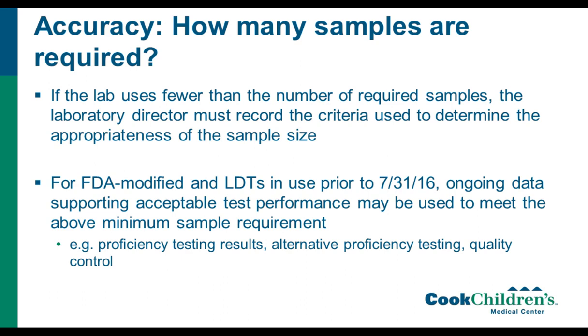CAP put these requirements for 20 specimens on their checklist in July of 2016. Prior to that, they didn't state specifically how many samples needed to be used. So if you validated an assay before that CAP standard came out, you still need some records of performance, but they say you can use proficiency testing results, alternative PT, swapping samples between labs, or quality control to show that you may not have had that many originally, but that your assay is performing as expected.